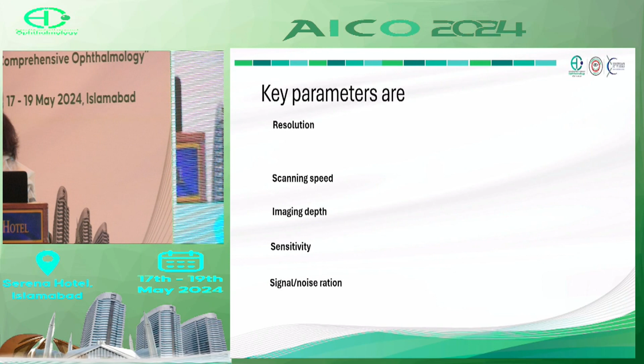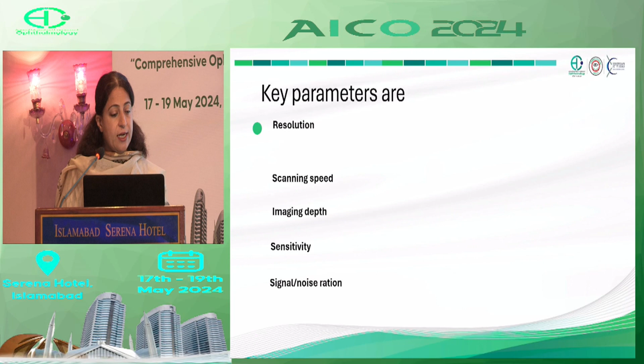A few key parameters should be understood. Resolution is simply the ability to detect two points as completely separate points. It has two types, axial resolution and lateral resolution. The axial resolution is the minimum distance that can be differentiated between two reflectors located parallel to the incident beam of light. The lateral resolution is the distance between objects lying side by side, perpendicular to the beam.